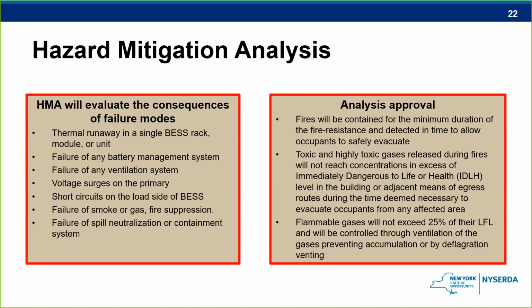So one of the first things you'll see in the new code is the hazard mitigation analysis. And this is only required for systems that are over 600 kilowatt hours, so your larger commercial systems. And this study is done to evaluate the consequences of different failure modes. If this, then what? And these are usually done by an engineering firm or the authority having jurisdiction, the town, whoever's permitting it, to determine the best approach on how to handle the failure should it occur.